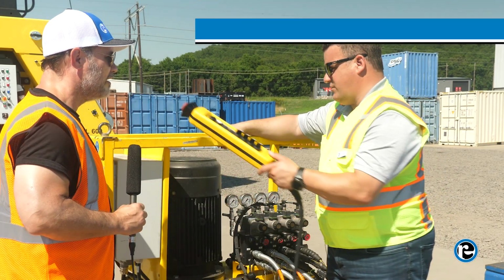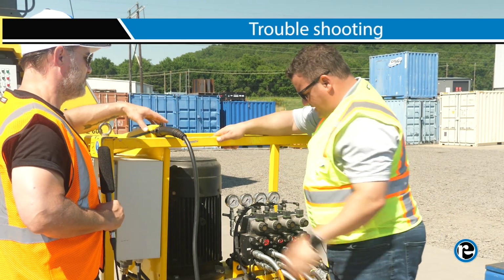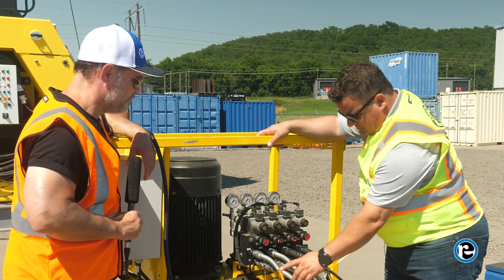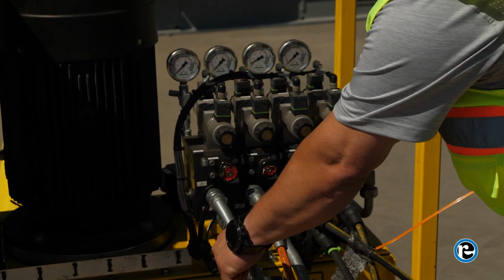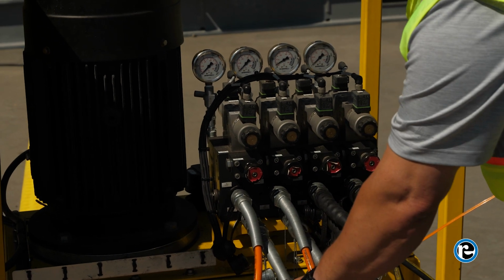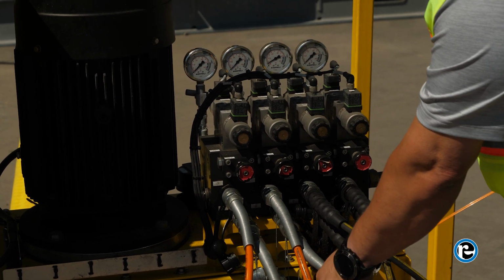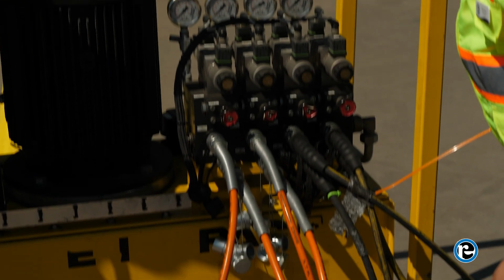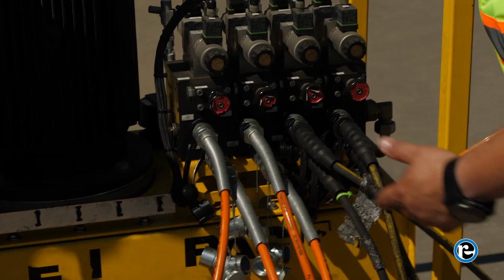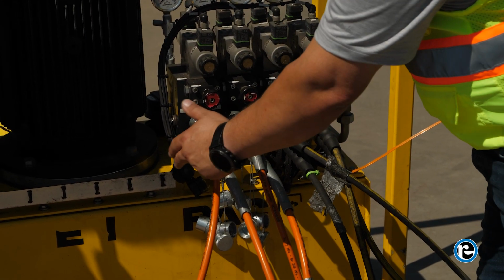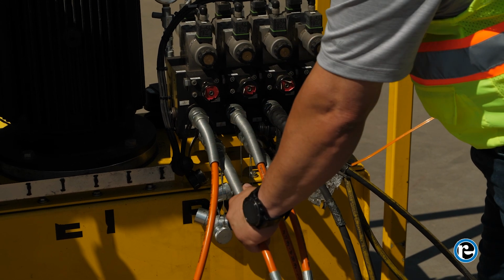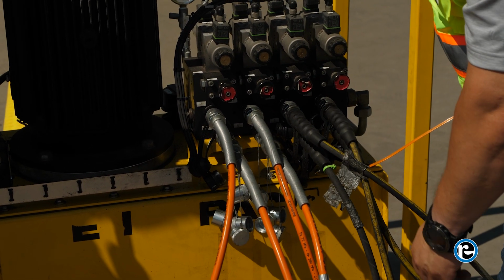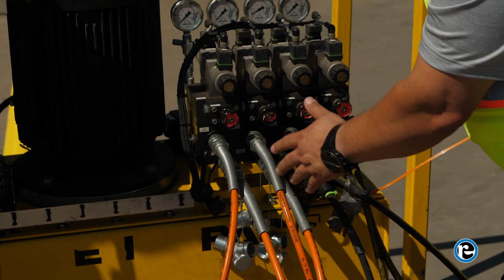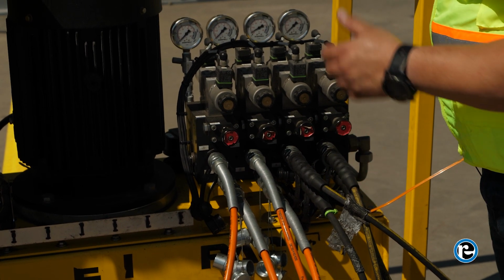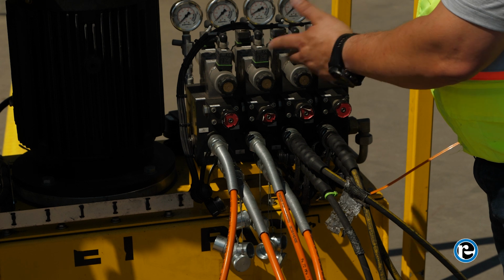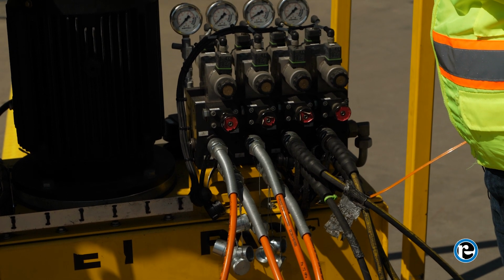As far as troubleshooting, a big thing people miss is they'll put hose 1 from cylinder 1 into the right spot, but hose 2 from cylinder 1 into the wrong spot. So it's always a good idea to check and make sure we get the hoses into the proper setup, number 1 for cylinder 1, number 2 for cylinder 1, and make sure you don't get those crossed, because it will look right up until you start to run it, and then you'll get a pressure spike or something else happen with the system.